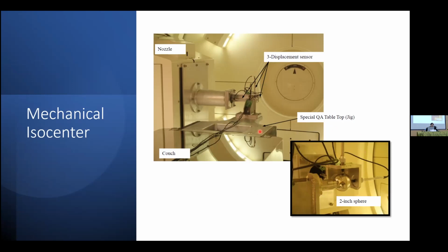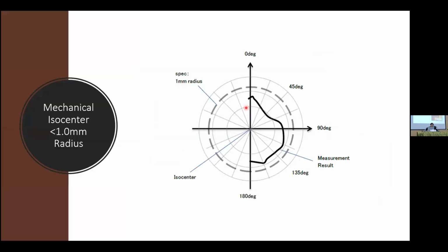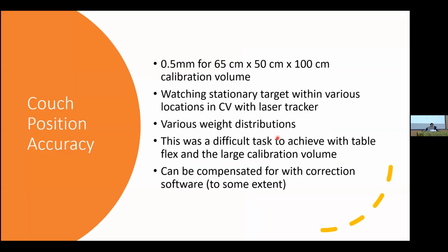But anyways, you've got to test the mechanical isocenter. And again, you have to have specifications. And this is just mechanical now, of the motion when it's going around. You have to have where you want it, and it has to be below a certain value, and it's not symmetric. So again, now it's moving slightly non-symmetric. And again, this could be a millimeter. And again, when we talk about things adding up, that's just the gantry.